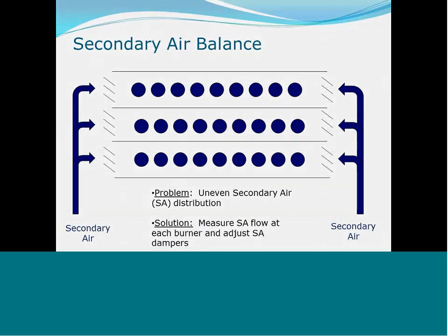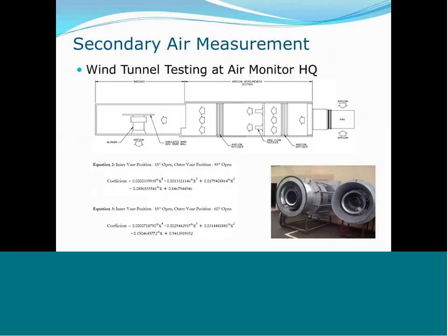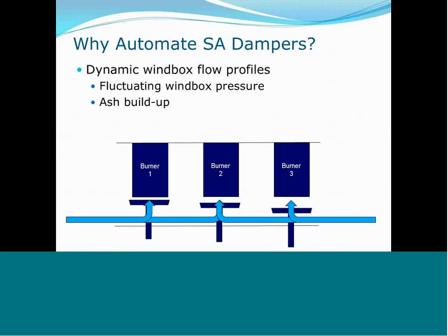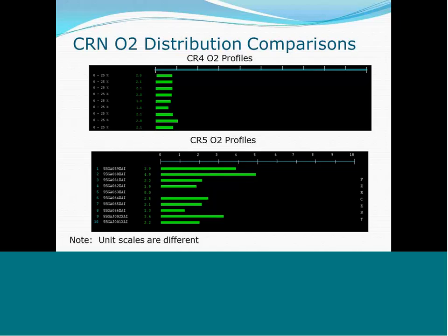So we calibrated their burner in the wind tunnel in Santa Rosa so that they had curves so that they would know exactly what the mass flow of air was moving through each secondary air duct. And then the idea is to use the adjustability of the secondary air register of the burner and adjust their airflows accordingly. And the result was, in addition to the unit that they put us on, Unit 4, they have an identical unit, Unit 5.